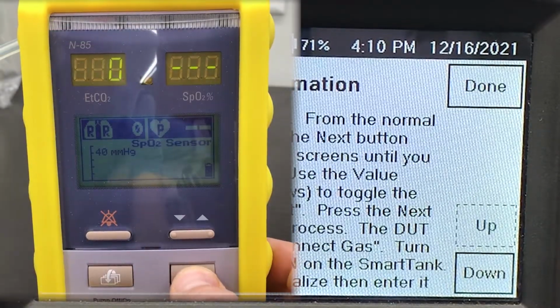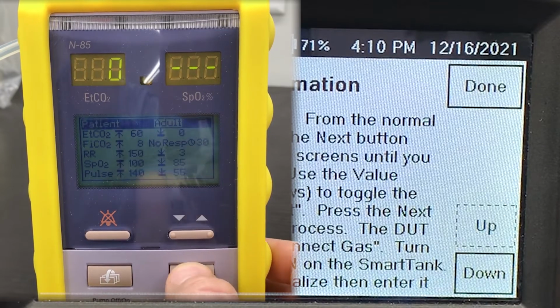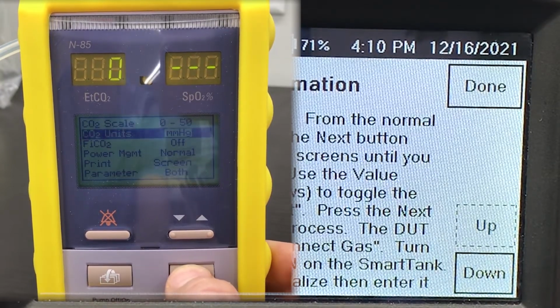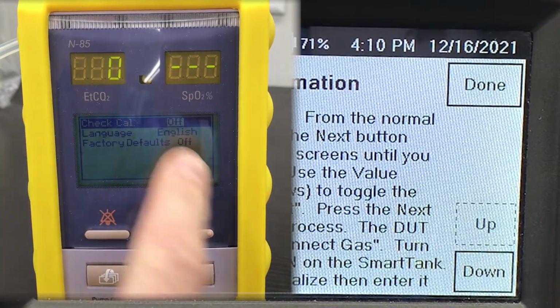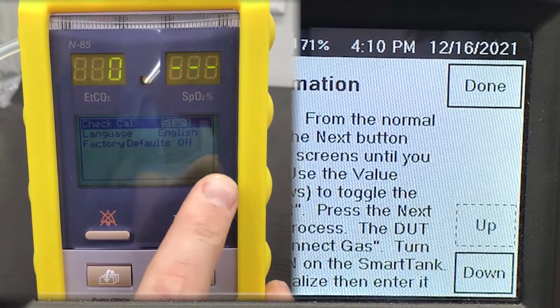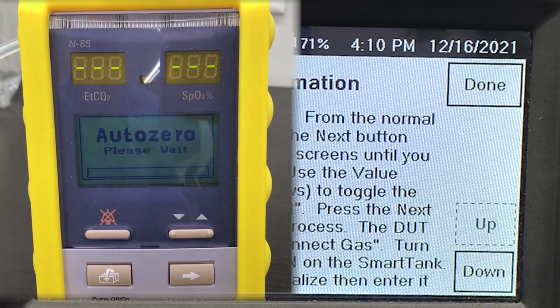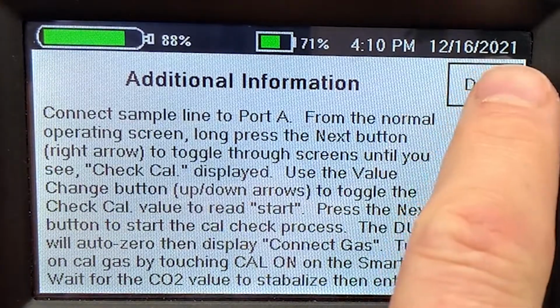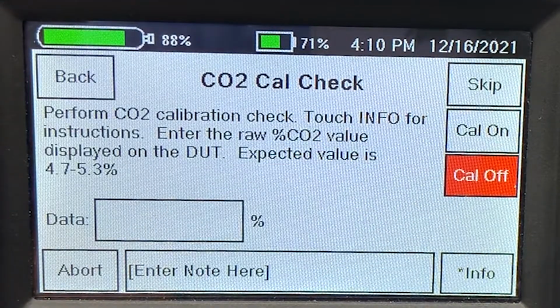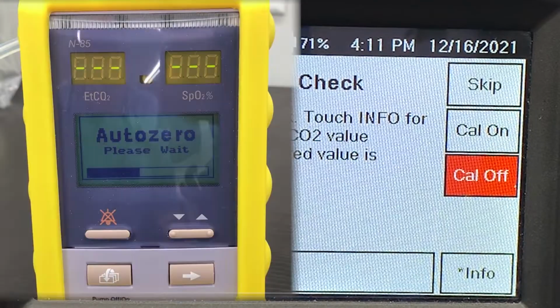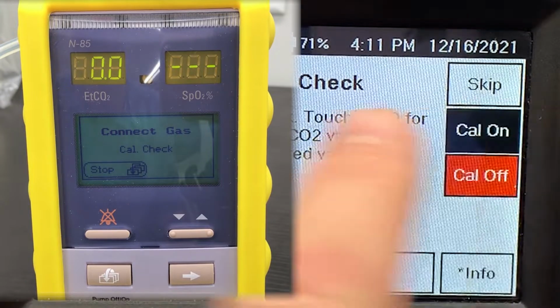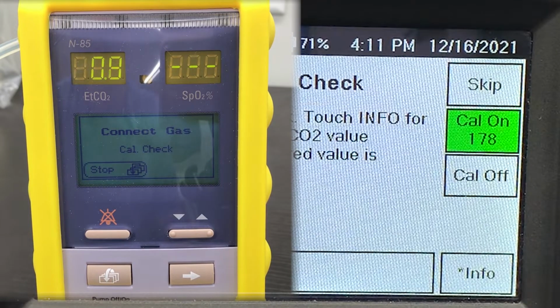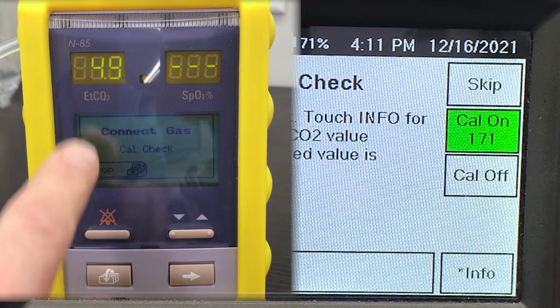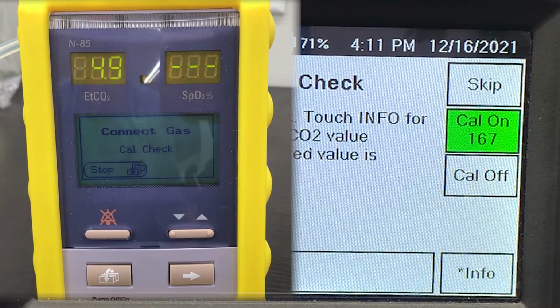So we start by long pressing the next arrow over and over again until we see CO2 cal check, and it says off. We use the up or down arrow here to change that to start, and then when we hit next, it will start. It will start out by auto zeroing the monitor. I'll exit out of this information screen. When it's done auto zeroing, we'll feed calibration gas. Okay, so we touch cal on the smart tank. The smart tank is now feeding calibration gas, and it's feeding just the amount of calibration gas that's needed, so it's not wasting. And all this mode does is tell the monitor to read the CO2 in percent.